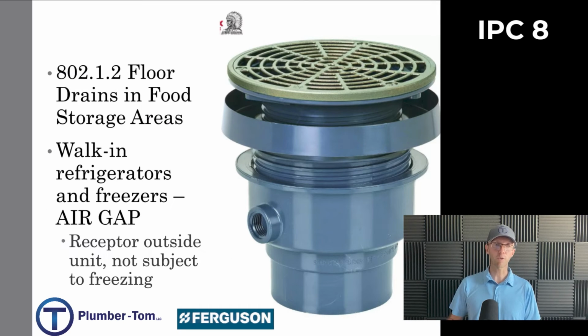802.1.2 talks about floor drains in food storage areas. So you're going to have a cooler or a freezer, these big walk-in freezers, right? Where you're storing foods, and those cooling systems are going to create some condensate. Those are going to be diverted to a floor drain or a receptacle through an air gap, as the code requires.